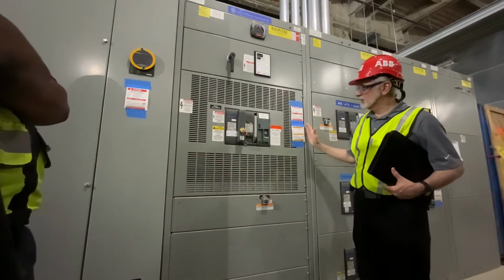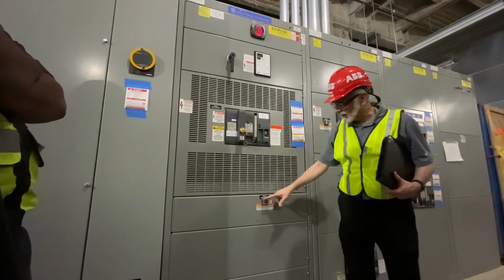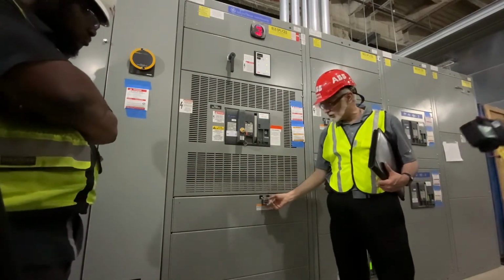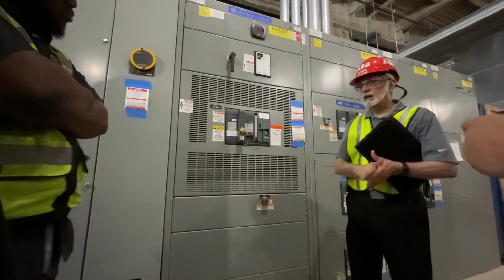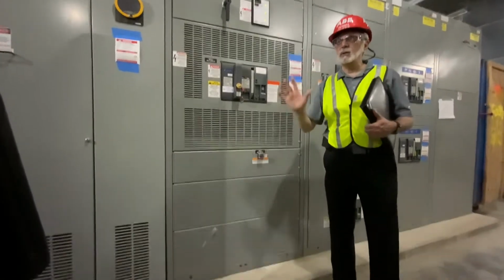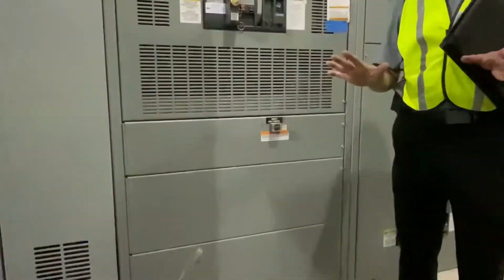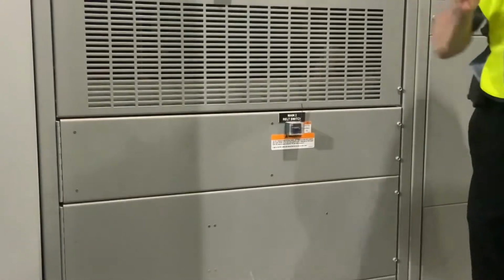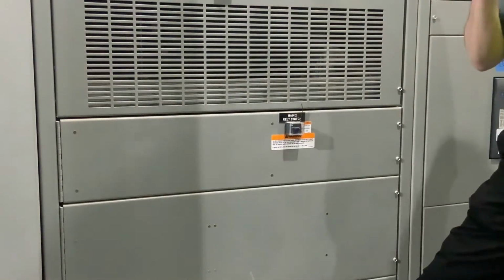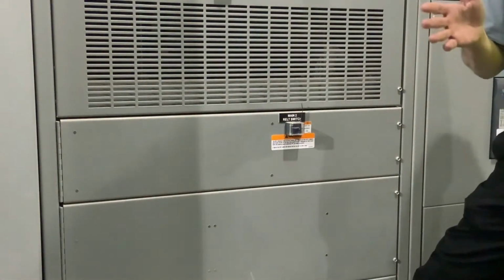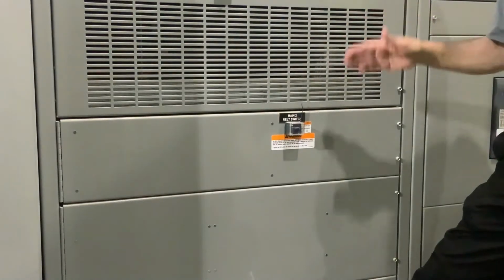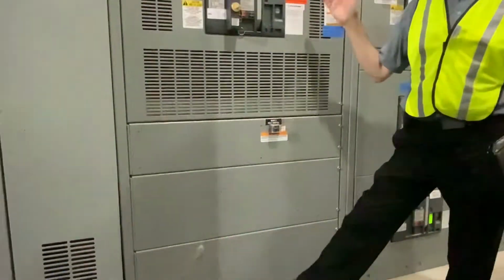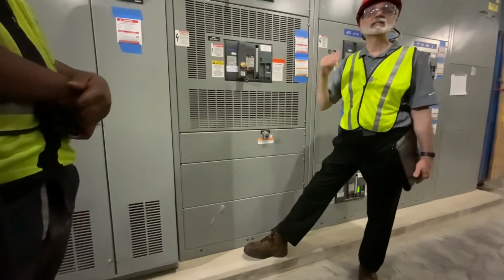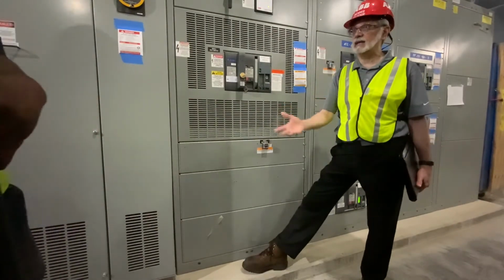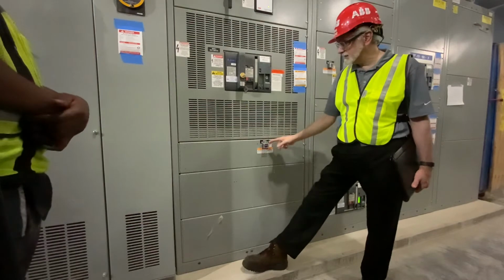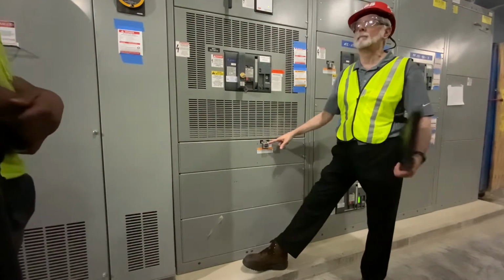The last thing I want to talk about in this piece of equipment is this device here. This is what we call a RELT switch, okay? And basically, again, we want to do everything in a de-energized situation. However, Philadelphia is under the 2020 National Electric Code. One of the things that's part of the National Electric Code is if you have a breaker over 1200 amp, you have to put in some sort of arc fault mitigating technology. The way that we do this is something called a RELT switch or a maintenance switch.